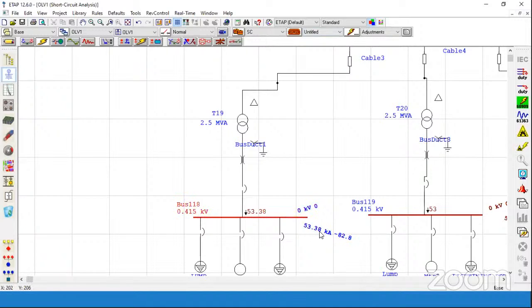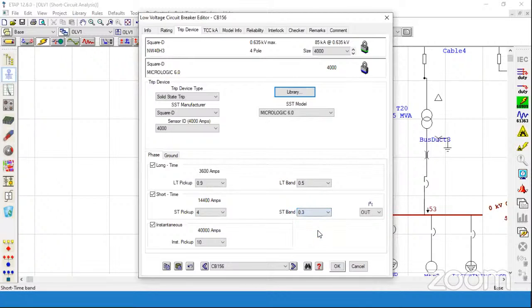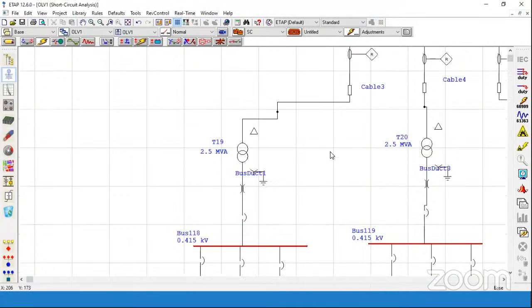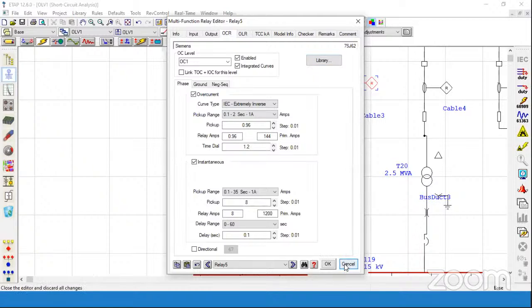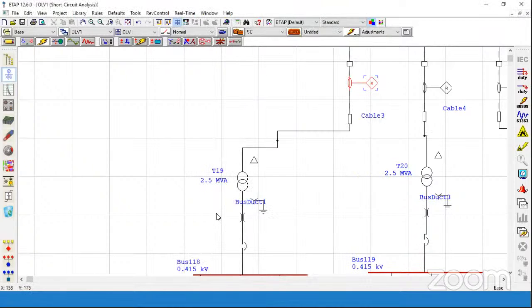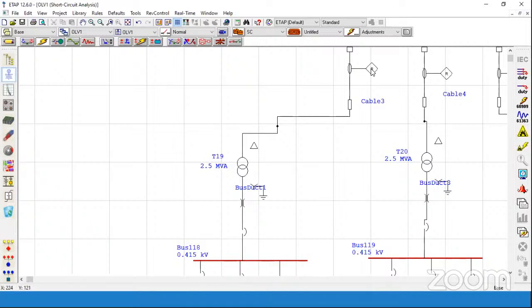Here we have 53.38 kiloampere fault current, and the time delay which we have set here is 0.1 seconds, maybe 100 milliseconds. Now the time grading margin is 0.2. Here this section will be set at 0.1. This section will be set with an additional time grading margin of 0.2, that is, it will be set to 0.3. Here we will go with 0.5 for IDMT, inverse definite minimum time of operation. We will go for backup protection at 0.5 seconds. So having this detail, we can calculate the parameters for this.